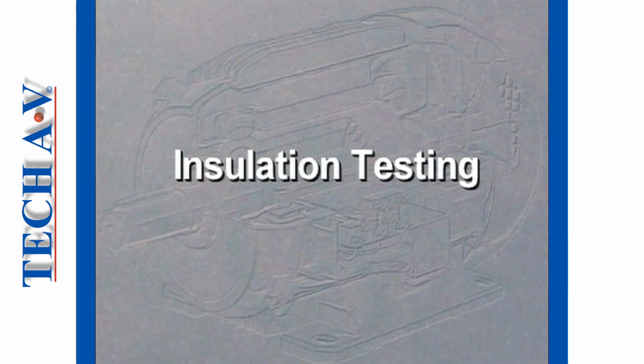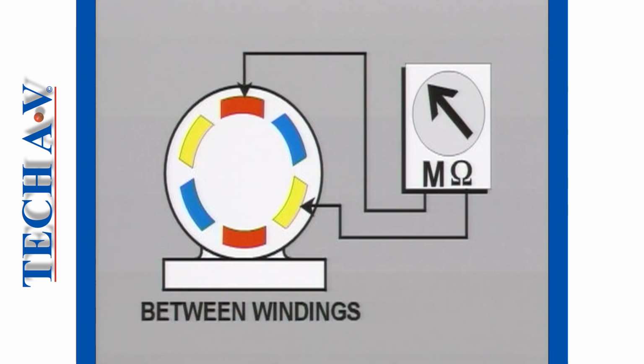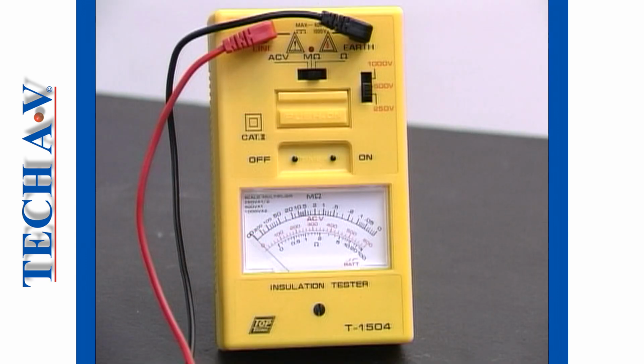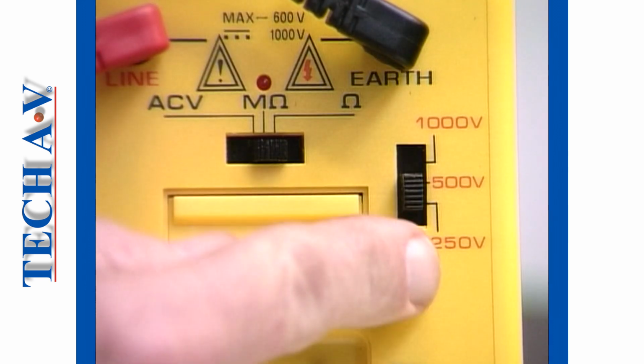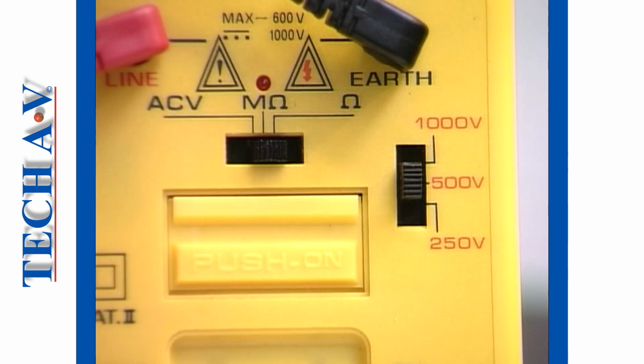Let's demonstrate how we test the insulation resistance. We begin the tests by measuring the insulation resistance between the windings. A high-voltage insulation tester, or Megger, is most suitable for measuring the insulation resistance. To prepare the instrument, set the output voltage of the mega to 500 volts and select the meg-ohm range.